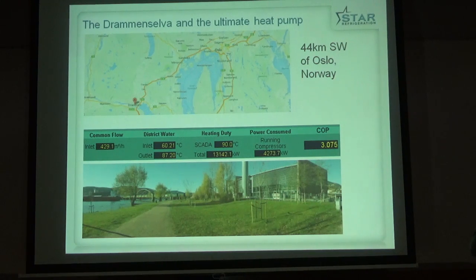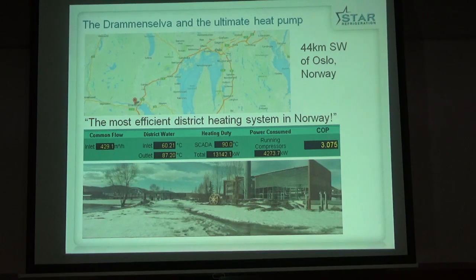They're very smart, the Norwegians. They know how to get the best out of everything. They described it as the most efficient district heating system in Norway. In winter time, what's interesting is that they tweak the conditions. They push the water flow rate up enormously because they're now having to do additional heating, still achieving 13 megawatts of heating. But this thing, that heat pumps get less efficient in the winter time. Here's the winter time condition, and the COP is 10% higher than it was in the summertime condition because of the way that they're operating the plant. So basically lots of clever tricks that you can play to get around the traditional challenges.